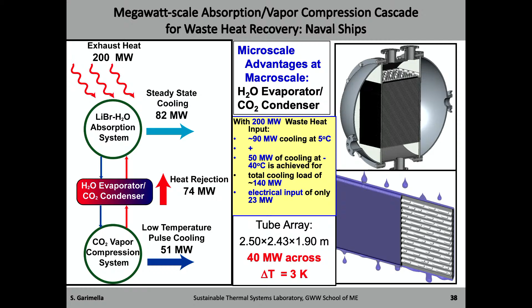The way we did this is by using flat tubes with microchannels in them. We would condense CO2 inside. CO2 is an excellent working fluid, and when you use microchannels, the heat transfer coefficient is very high. Falling film water also has very high heat transfer coefficients, and both are isothermal processes, so with just a delta T of 3 degrees, we were able to deliver 40 megawatts across a fairly small package.